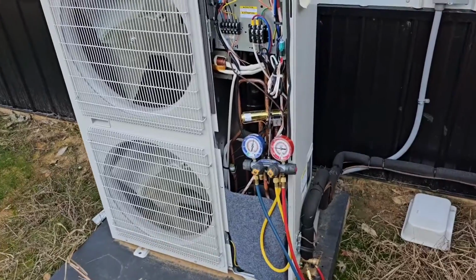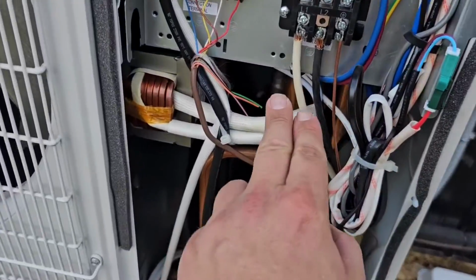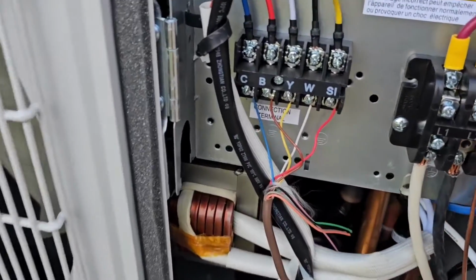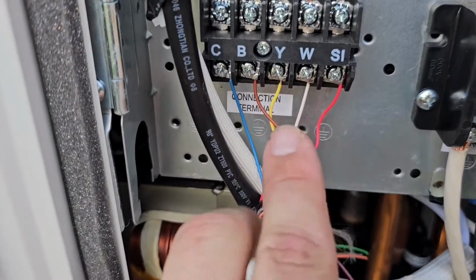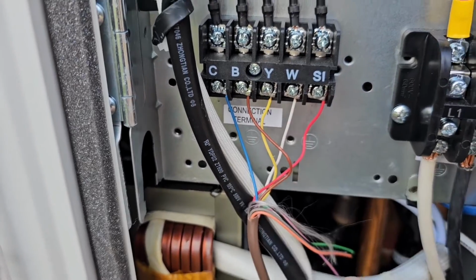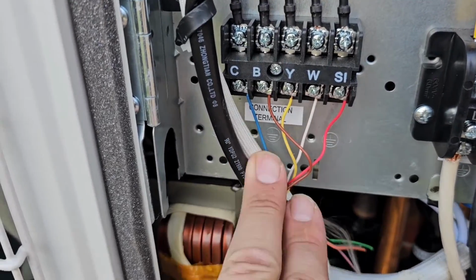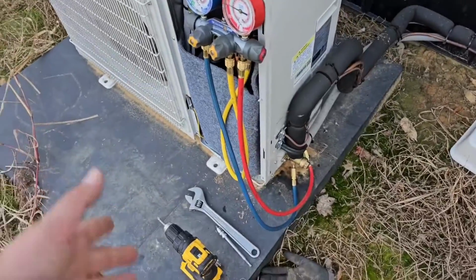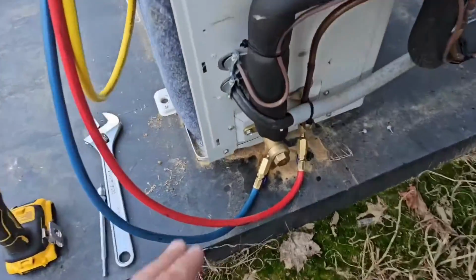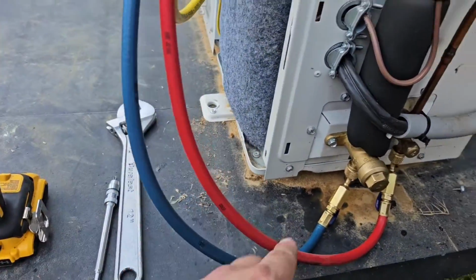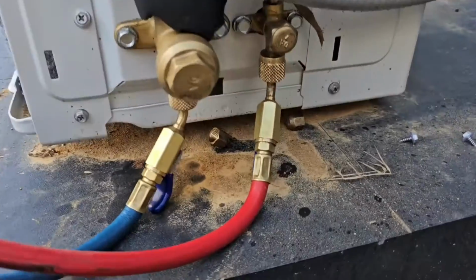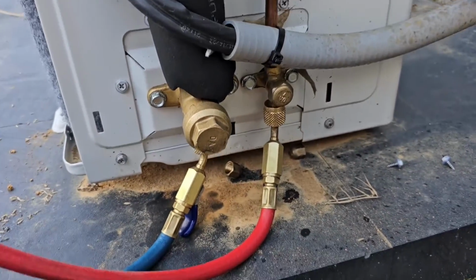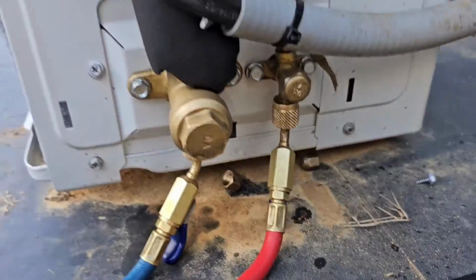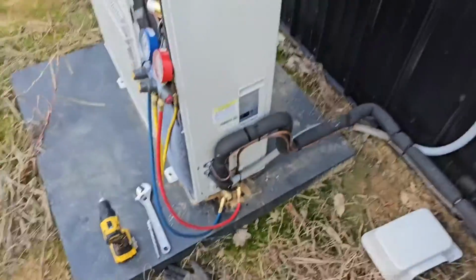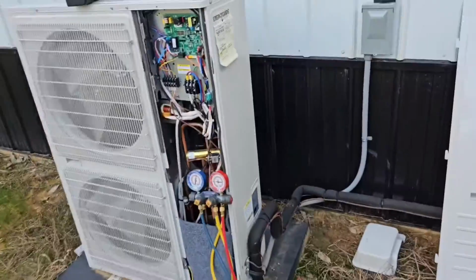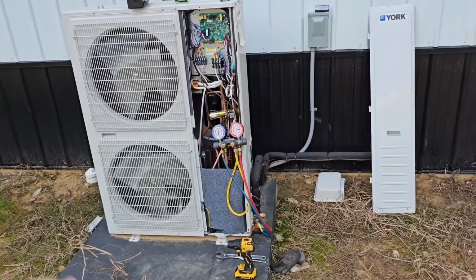It's beautiful. Just finished wiring the outdoor unit. I've got my power here, my low voltage here. I always start on the outdoor unit and I either write down or take a picture. That way I know what color I use for what terminal. Also, it may be a good idea for you to install some blocks. That way you can lift up the unit so you can actually connect your hoses to the service valves, because you can see it's pretty tight. So give yourself enough room. Looks good. Let's go inside.